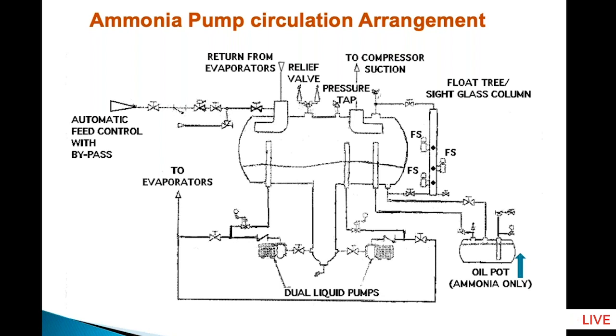And you circulate liquid ammonia of a required temperature through these vessels. The liquid ammonia comes down. The liquid ammonia circulated is normally about 4 to 5 times the actual evaporation taking place. So the mixture of a little bit of gas, one part gas and 3 or 4 parts liquid, returns back to the LP vessel, and then only the pure gas is sucked by the compressor. The compressor then does not get any liquid stroke. It is free, only ammonia gas is sucked by the compressor.